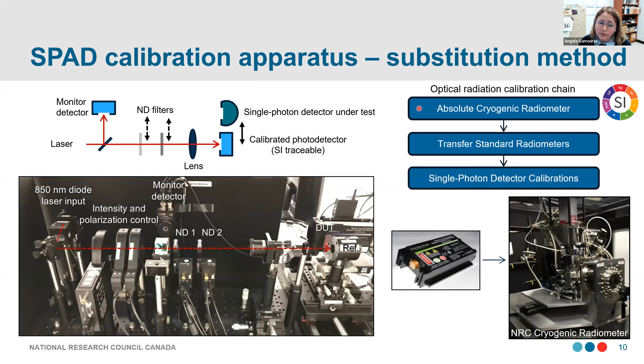The cryogenic radiometer is a type of electrical substitution radiometer, which is calibrated traceable to electrical units. In this cartoon, it shows a bit how it works, where we have a really black radiation absorber, which absorbs our optical radiation. If we open our shutter, our optical radiation hits our absorber, and the incident radiant power is measured by determining the amount of electrical power required to cause the same heating effect on this absorber as an incident amount of radiation. Essentially we have a temperature sensor, so we can measure how much the temperature changes when our optical radiation hits this cavity.